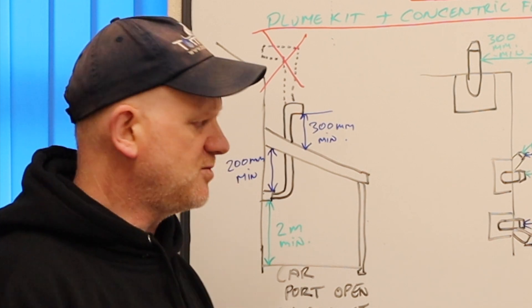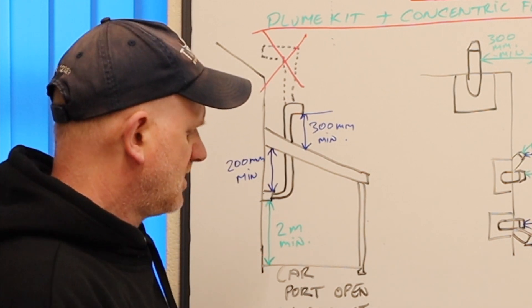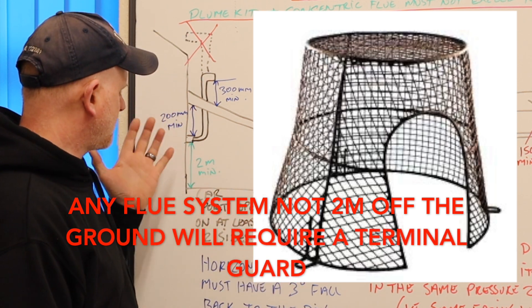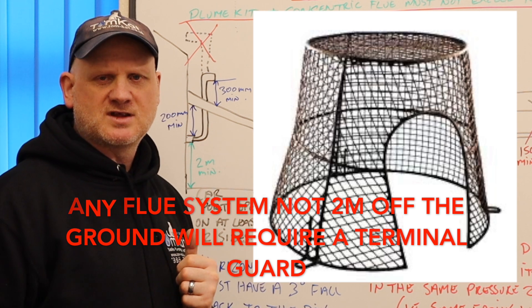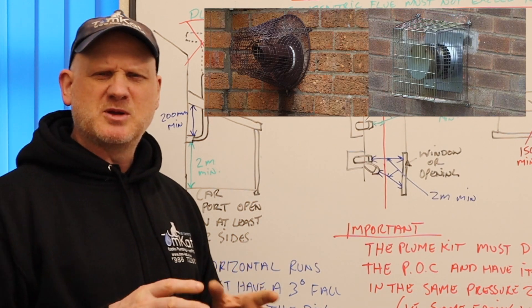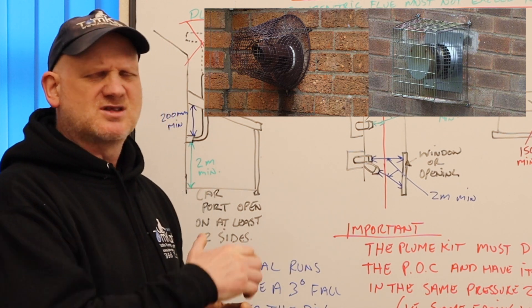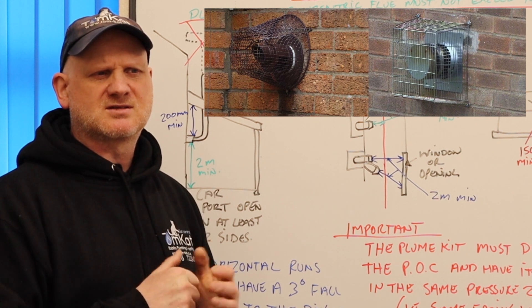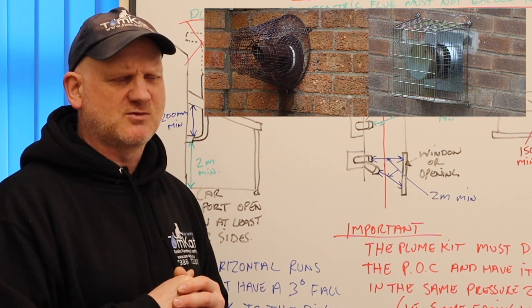If we're less than 2 metres off the floor with this system, then we'll still need to put a terminal guard. And the terminal guard is there to protect the flue system from damage. The terminal guard used to be there to stop people getting burned, but there's no heat coming from this now, so we're using the terminal guard because BS 5440 says we have to.